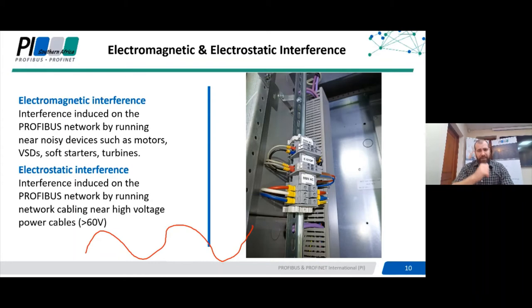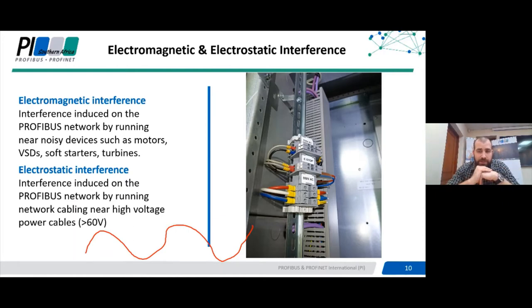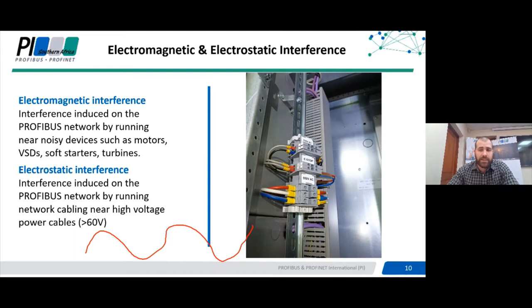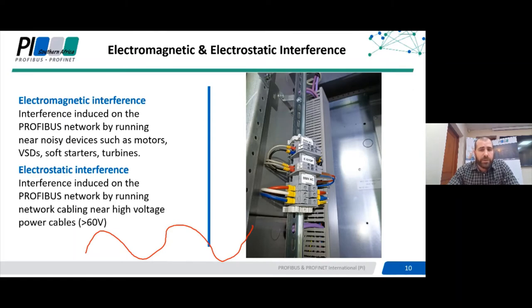Once you've identified EMI interference in your network, a simple fix is to firstly, where practically possible, move your Profibus cable away from the source of interference — at least 20 to 30 centimeters away from any high voltage cables. By high voltage I mean anything typically above 100 volts AC or DC. There is a guideline depending on voltages: above 400 volts requires over 20 centimeters separation, below 400 volts is normally about 10 centimeters. Avoid running over any VSDs within panels where not completely necessary.